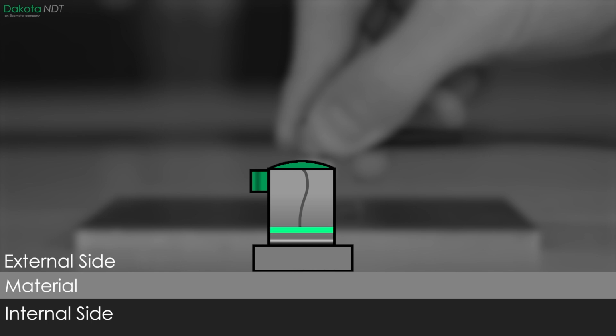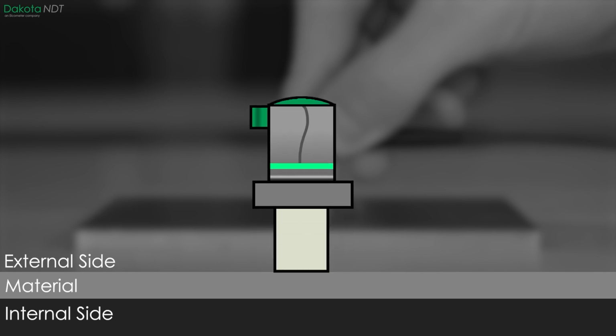However, measuring thin materials means that the ultrasonic signal will return to the transducer incredibly quickly, meaning there's not always enough time between the pulse leaving the element and the echo returning. This is why, when using a DakotaNDT PCX, single element transducers use a delay line to both increase the amount of time between the pulse being sent and the echo being received, and also make sure that the material being measured is outside of the transducer's near field zone, which ensures more accurate results.